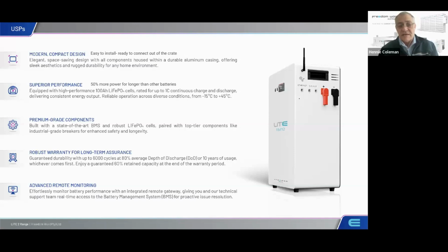When it gets to 60 degrees and the temperature exceeds that threshold, the BMS will physically trip and shut down the entire battery, de-energizing it from the circuit to protect the battery as well as the environment from a possible safety event. In terms of batteries going into the market now on the CSE listing, all of our batteries comply with the latest battery standards where both poles are fully isolated, built into the battery itself, so you don't need external isolators -- it all comes built in and embedded.